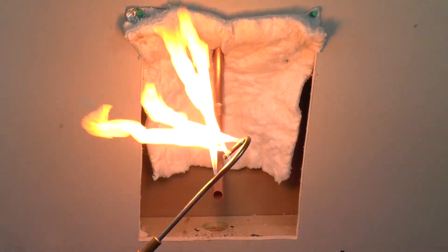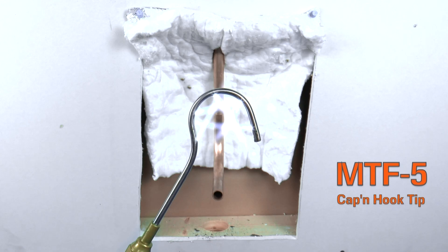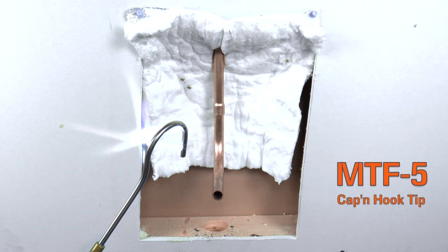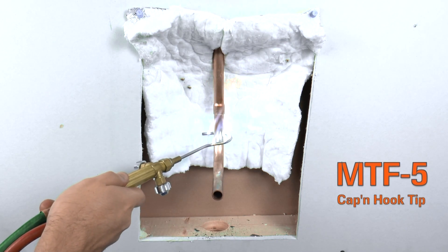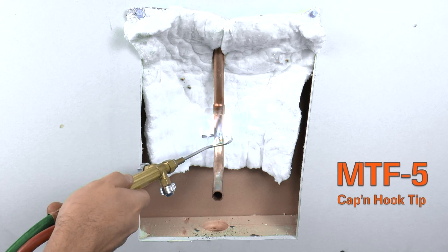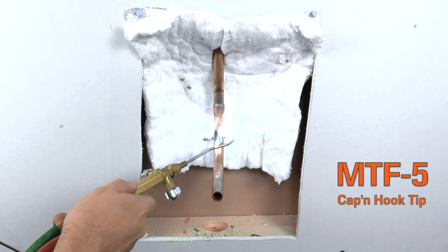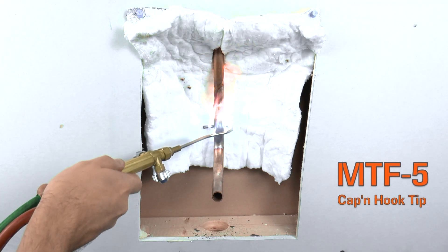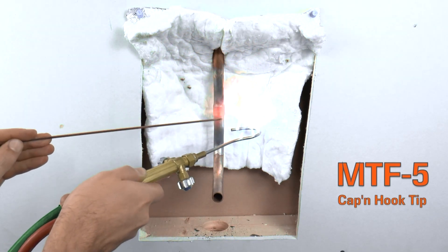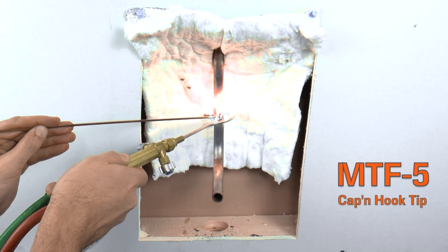Now let's braze this joint using a Uniweld torch. Another great tool for brazing in a small space is the MTF-5 Cap'n Hook tip that features five flames for 100% wraparound on the tubing. There is no heat on the back of the tip and the 45-degree flame angle directs the heat down the tubing and away from any nearby sensitive materials. The pipe will heat evenly and quickly, reducing the time spent with the flame in the wall. As the tubing heats up and becomes red, feather the flame off and on the tubing to control the heat and prevent melting the copper. The capillary action of the alloy and the even heat distribution causes the alloy to flow around the joint completely. The alloy will always flow towards the heat, so move the flame slightly behind the joint to draw the alloy inside for a solid, leak-free connection.